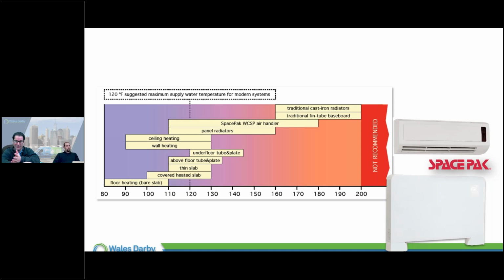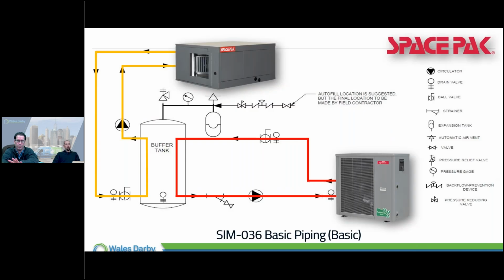That's a great question. If you didn't see what the visual was, that is the chiller, the air-to-water unit. You call it a condenser, we call it a chiller or heat pump, it depends on the stage. So that's changing what we're doing here. Your mono block, right, this outdoor unit we're talking about. Being a mono block, really, it is the condenser and the evaporator in one, a full package system. As far as coils go, there's a refrigerant-to-water braze plate heat exchanger, or a tube and shell.